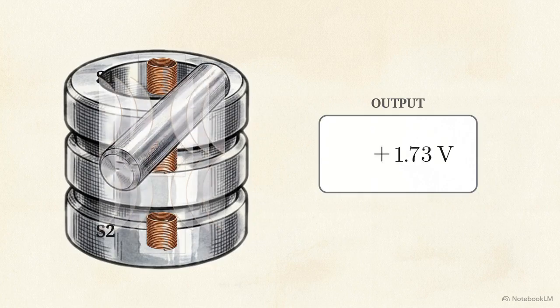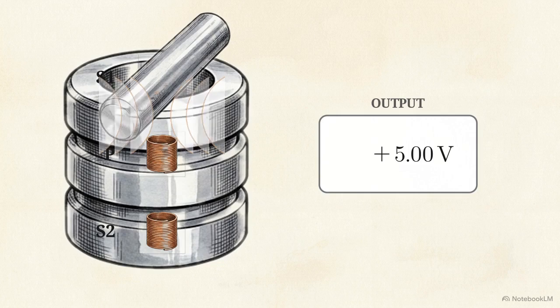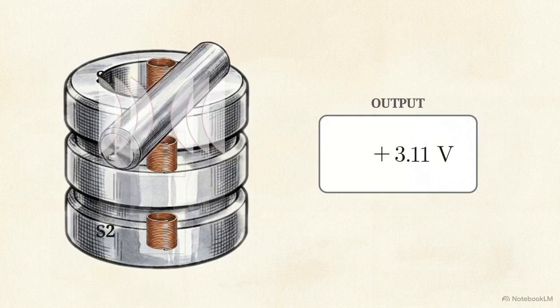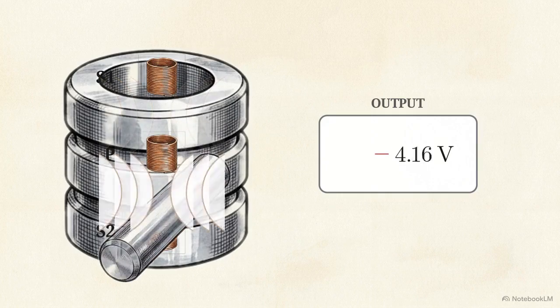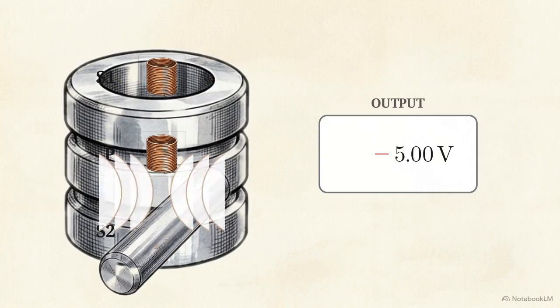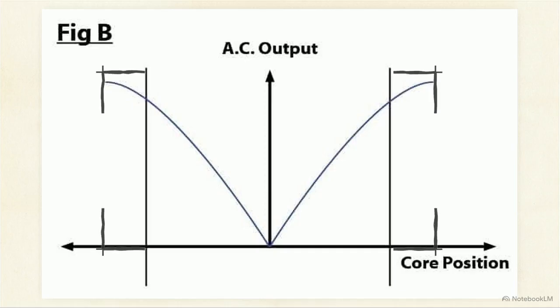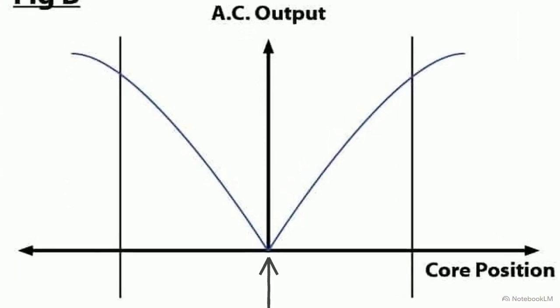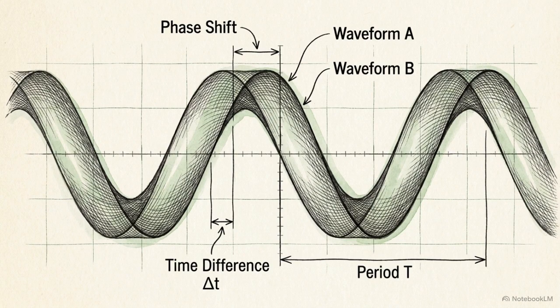Moving the core upward increases the magnetic coupling with S1. This induces a higher voltage in the first secondary, creating a positive output. Moving the core downward shifts the coupling toward S2. The output becomes negative, signaling a 180-degree phase shift relative to the primary. This makes the V geometry. This V-shaped curve represents the LVDT's output signal as the core moves through its range of travel. The central intersection on this graph represents the absolute null point, where displacement is 0. Engineers use the phase of the signal to determine which side of that null point the core is on.